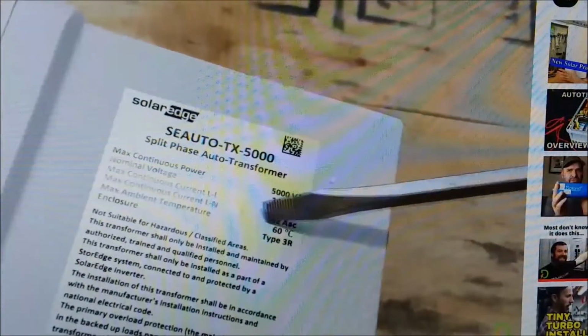Let me see if I can find a 21 amp breaker, or I might have to put it on a 20 amp. If your current line to line is 21 amps, we're going to look at the auto transformer, on a 30 amp breaker right now. This is how you make your 120. If you guys know the answer, let me know in the comments below.